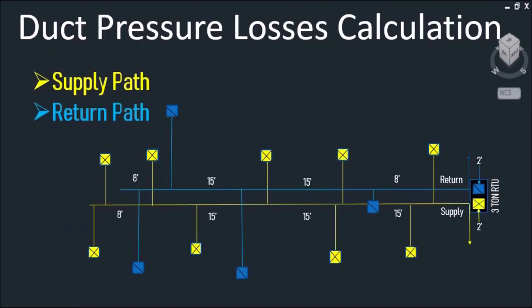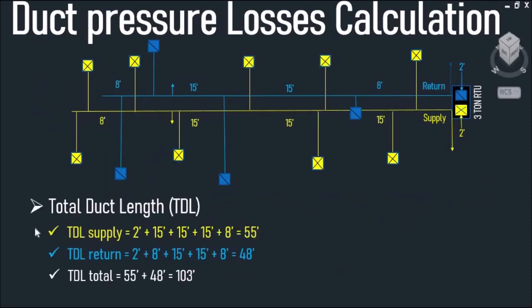The first thing we have to do is measure and calculate the total duct length of our supply including our return duct along a critical path. As you can see, I've drawn a single line duct diagram showing the total length of our supply and return duct. The supply duct is 2 feet plus 15 feet plus 15 feet plus 15 feet plus 8 feet, and the return duct is 2 feet plus 8 feet plus 15 feet plus 15 feet plus 8 feet.